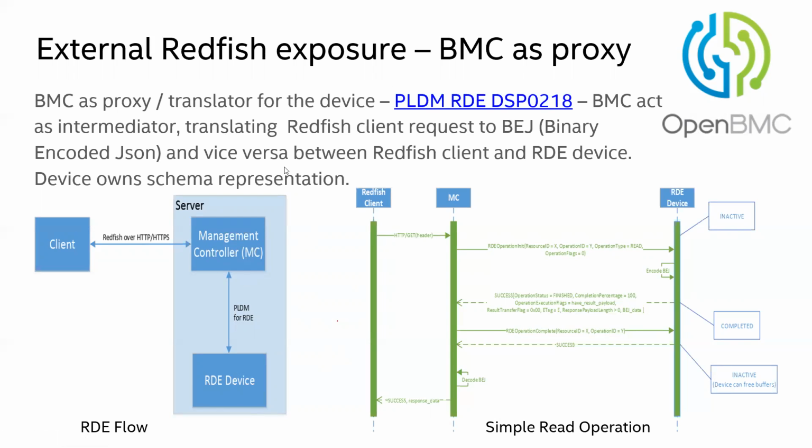The reason is that BMC is needed anyway. That is monitoring and control, in terms of regular sensor monitoring and taking certain actions based on an add-on card. Let's say that when we have an add-on card, we may need to do certain thermal management as part of the add-on card's temperature. Sometimes if the temperature of the card is too high, we may need to spin up the board fan speed also. So in that way, the BMC anyway has to go and read certain temperature sensors in the add-on card, and it has to represent them.